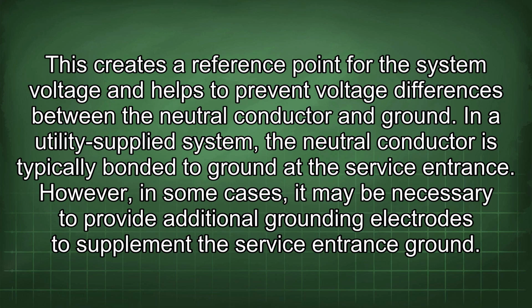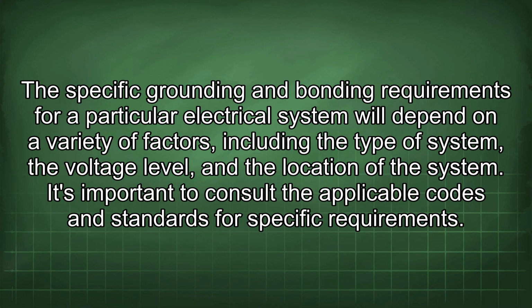However, in some cases, it may be necessary to provide additional grounding electrodes to supplement the service entrance ground. The specific grounding and bonding requirements for a particular electrical system will depend on a variety of factors, including the type of system, the voltage level, and the location of the system. It's important to consult the applicable codes and standards for specific requirements.